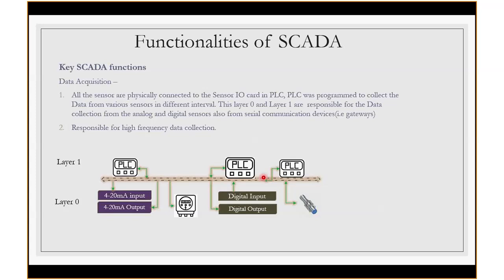We don't want to take the data too often, as that will create junk in the data. Junk of data means if the data is not varying but you keep taking it at high frequency, there's no use. That's why various sensors are read at different intervals. Layers 1 and 0 are responsible for data collection from analog and digital sensors. In some cases we may also connect serial communications like RS-232 or RS-485 at layer 0, and it is also responsible for high frequency data collection, even millisecond data collection. That also comes under this data acquisition layer.